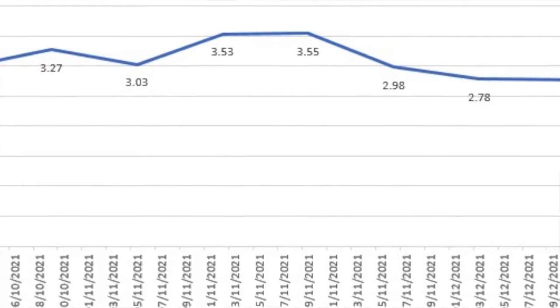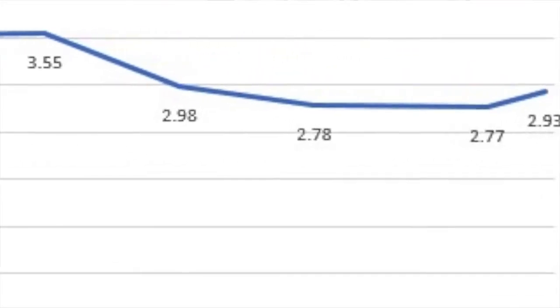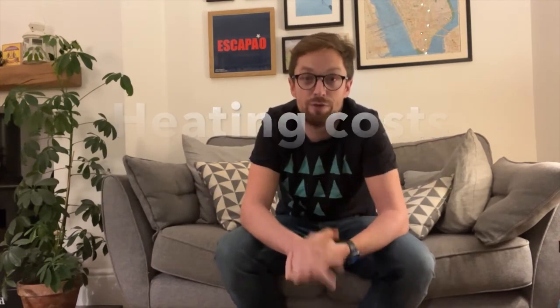After that first four months, I've started taking readings at least weekly and plotting usage, emissions, costs, and efficiency for the foreseeable future. The last couple of months have given me much more data on how the system responds to heating and hot water, particularly as the temperature begins to drop — it's December now. For the first four months we had a COP of three, and as we began to use more heat relative to hot water, the efficiency started going up from three to 3.3, back down to three, up to 3.5. Then over the last couple of weeks it's gone down to 2.8 and back up to 2.9. This means for every unit of electricity, we're getting about 2.8 units of heat. For the full month of November, our heating costs were just over £58. If using gas for that heat, it probably would have cost us about £40.